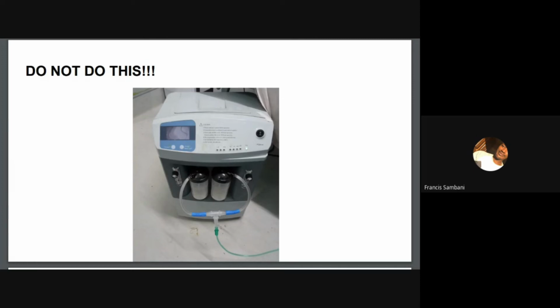Moving on, when you're using a flow splitter with an oxygen concentrator, and this might also be with an oxygen cylinder, but in this case with an oxygen concentrator, you should make sure that the flow on the oxygen concentrator is at least 1 liter per minute more than the total requirement from all the ports in use on your flow splitter. If you're trying to get 3 liters per minute from your flow splitter, you should make sure the flow meter on the oxygen concentrator is set at 4 liters per minute. This is what the statement is trying to say.